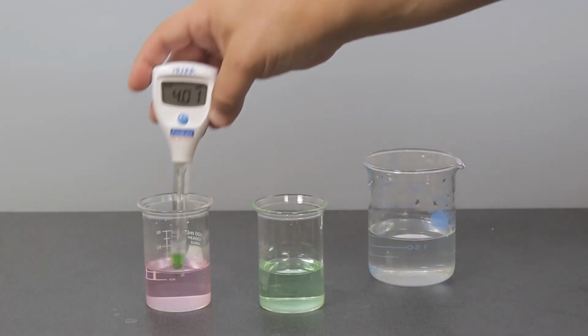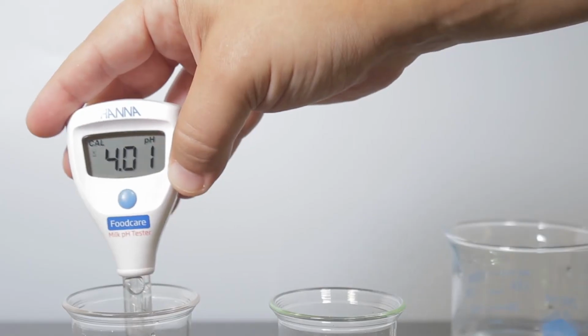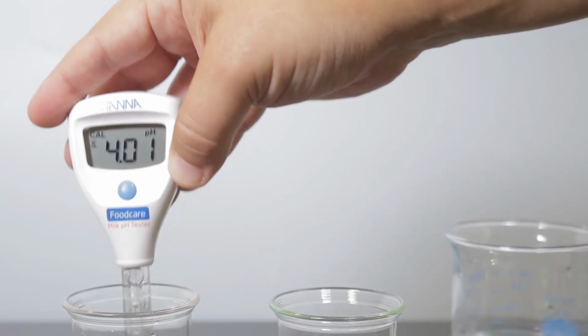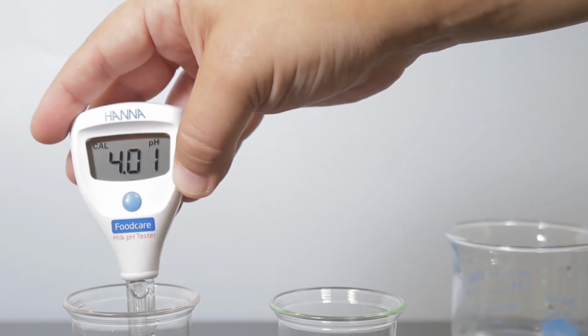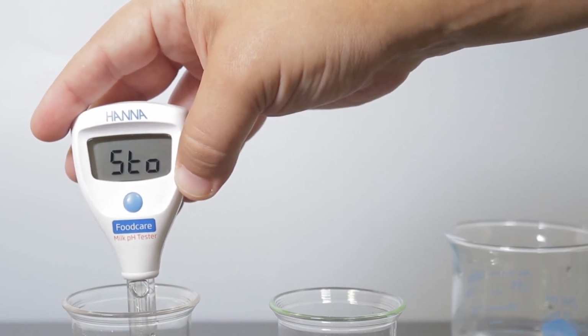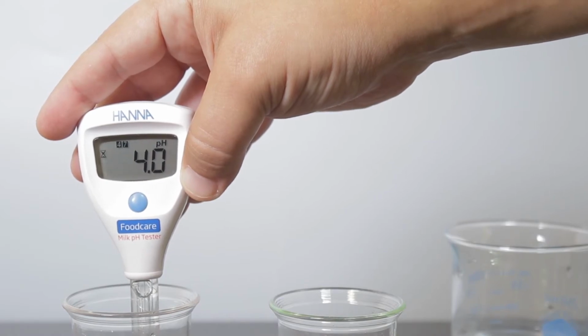Rinse the electrode again and place the tester in your pH 4.01 buffer. Once the second calibration point is stable, Store will appear on the screen, confirming that the 2 points are recorded, and it will return to the measurement mode.